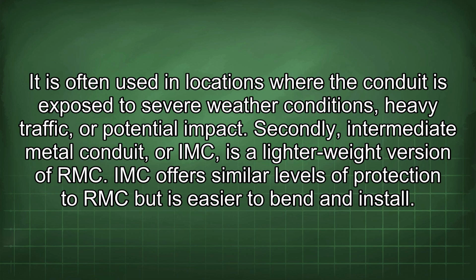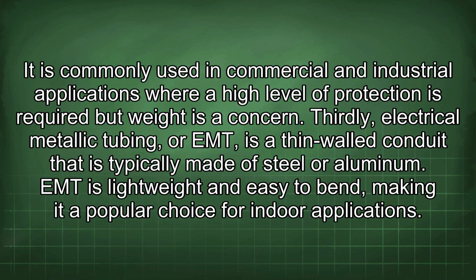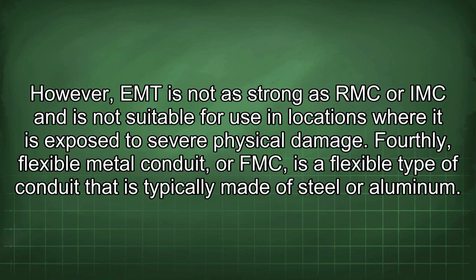Secondly, intermediate metal conduit, or IMC, is a lighter weight version of RMC. IMC offers similar levels of protection to RMC but is easier to bend and install. It is commonly used in commercial and industrial applications where a high level of protection is required but weight is a concern. Thirdly, electrical metallic tubing, or EMT, is a thin-walled conduit that is typically made of steel or aluminum. EMT is lightweight and easy to bend, making it a popular choice for indoor applications. However, EMT is not as strong as RMC or IMC and is not suitable for use in locations where it is exposed to severe physical damage.